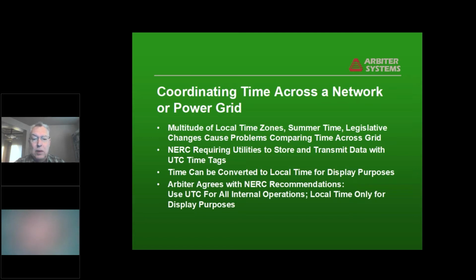The problem with coordinating time across any kind of a network, including the power grid, is all these local time zones and summertime changes and legislative changes causing it to be different. And those cause problems. And NERC and the utilities and the regulators have noticed this. And so now NERC requires utilities to store and transmit data using UTC. Now, that doesn't mean you can't have local time on your clocks in the substation or in your control centers. You certainly can. Most of your employees that are going out to work on the equipment will be operating on local time.